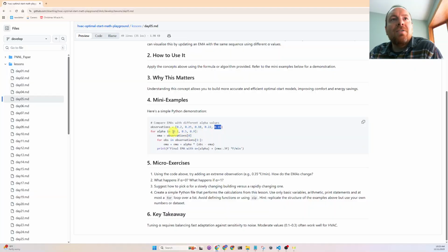Then these alpha parameters, we can tune basically. We talked about this yesterday. We could have one random outlier, caused by occupancy or weather, that gives the degree per minute calculation a little different effect. These alpha parameters will smooth out that data.